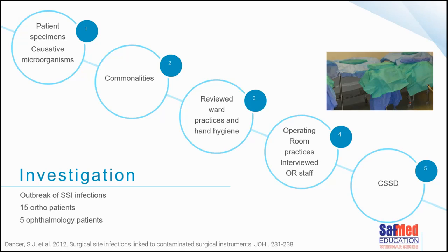They started to look at commonalities: what about the surgeries was common? Were the patients nursed in the same ward? Were they nursed by the same staff? Did they undergo similar procedure types? Were the surgeries conducted in the same operating theatre? Same theatre staff? Same room? Same anaesthetist? They reviewed ward practices and hand hygiene processes, then moved to the operating room. While interviewing operating room staff, the staff said they had noticed a lot of damp packs of late — packs that were damp and stained, with an increase in that occurrence.